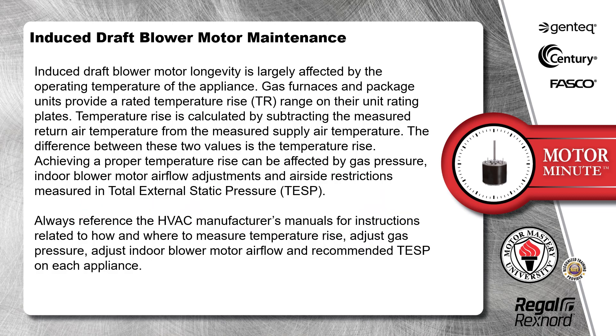Induced draft blower motor longevity is largely affected by the operating temperature of the appliance. Gas furnaces and package units provide a rated temperature rise, or TR, range on their unit rating plates. Temperature rise is calculated by subtracting the measured return air temperature from the measured supply air temperature. The difference between these two values is the temperature rise.